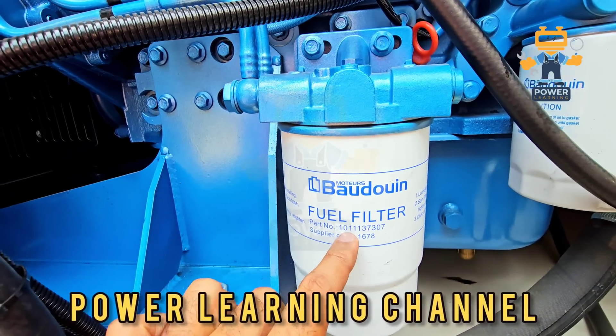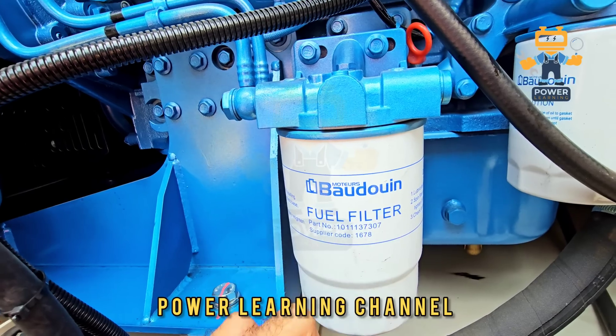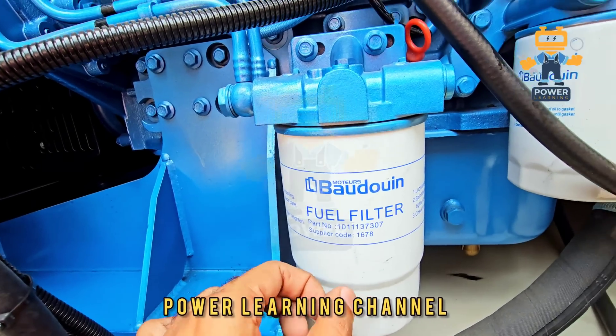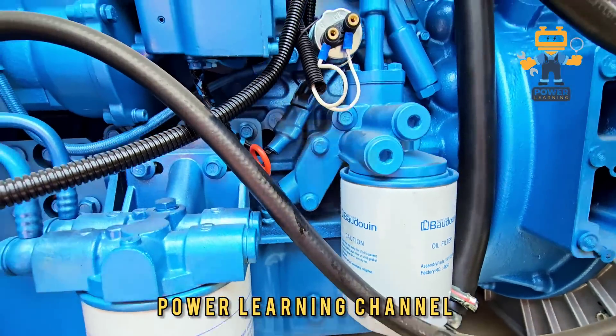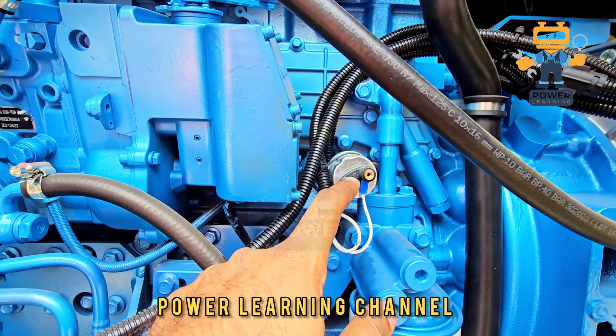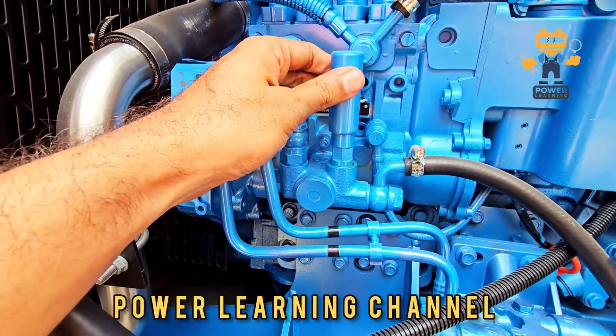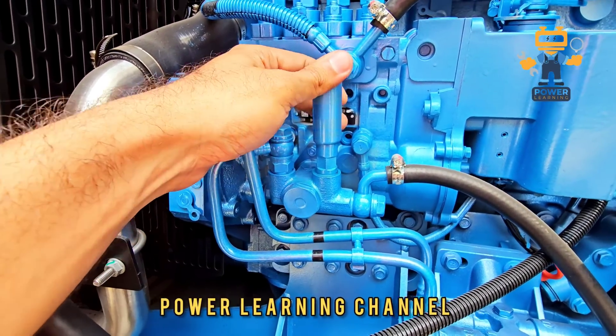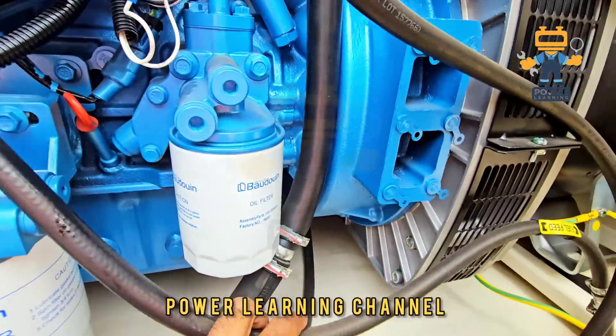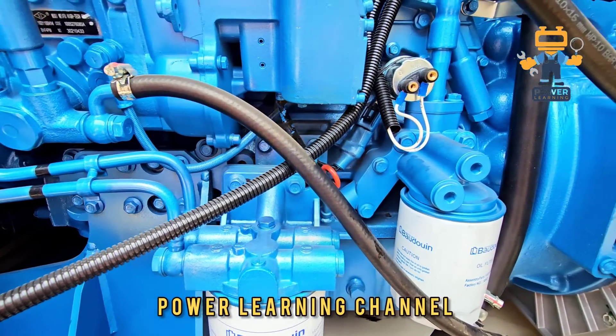The fuel filter number is 1011137307, supplier code 1678. This is the fuel filter, and this is the oil filter. Here we have an oil pressure switch and sensor — both. This is the priming pump, the fuel priming pump. The fuel feed line goes from the fuel priming pump to the fuel filter and then returns to the fuel pump.